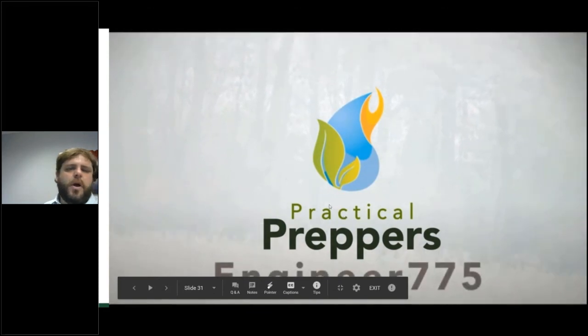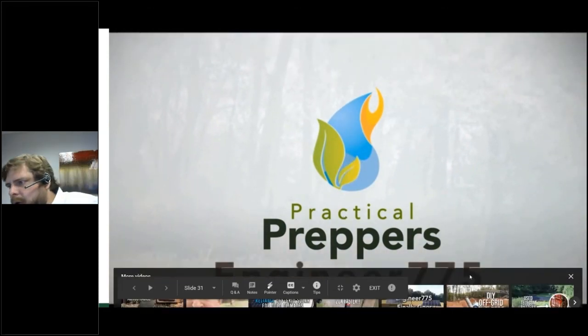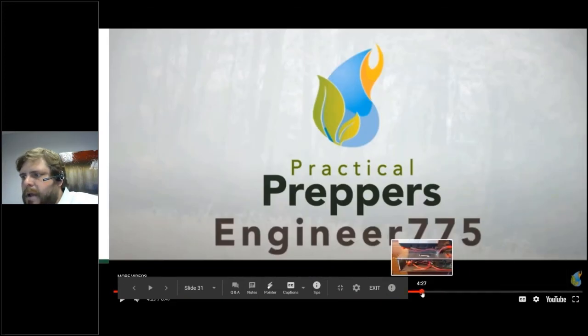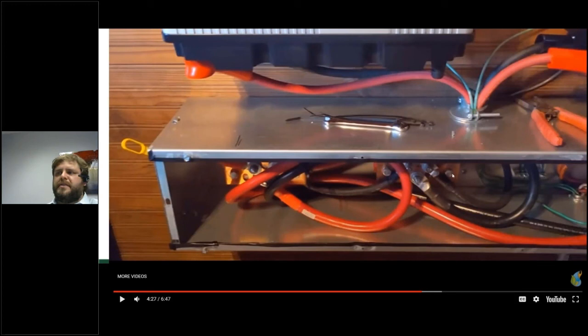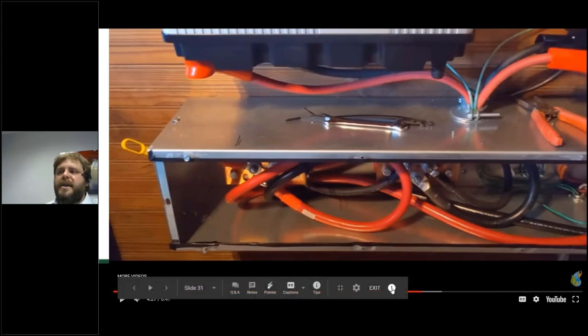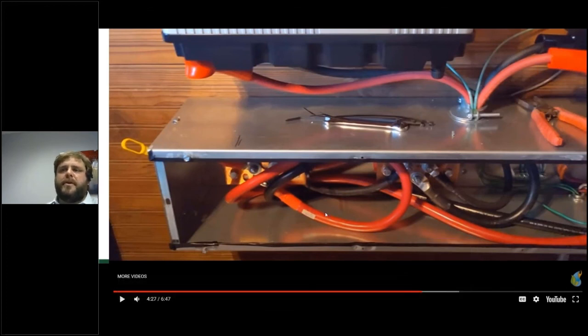Here's a nice video on YouTube that goes through an eflex installation. We're already over time in class, so I'm not going to cover the whole thing, but you can see he's putting these bus bars inside the gateways. Another nice thing he did was, these cables between the eflex and the bus bars, he pre-made them in advance and cut them all to the same length, so that the cable runs between the bus bar and each individual battery are the same length. It's not that the batteries are all located the exact same distance from the bus bar, it's that the cables to connect point A to point B are the same length.